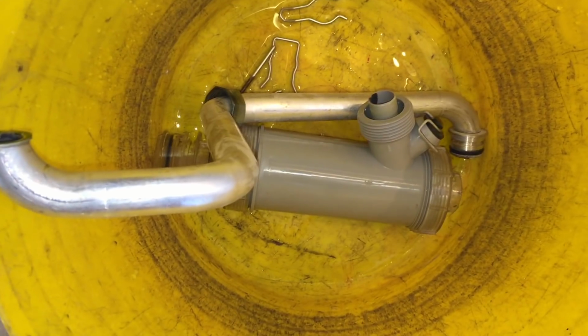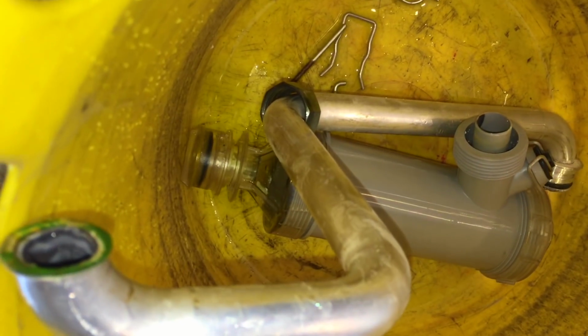Okay, so while I was cleaning that recuperator out, once I started flushing it through with water, the water was backing up and pouring out the front of it. So I had to strip all the condense pipe out, which was all blocked. The condense trap was all blocked, so that had definitely been causing an issue. I had to pull all of that stuff out and unblock it - that took ages, and that trap was so fiddly.